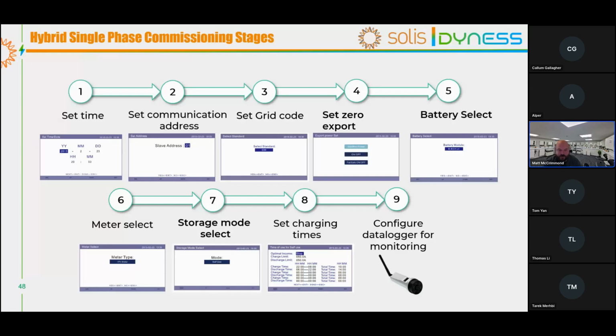You then go into battery select. So in this case, you're going to select Dyness, which is basically the CAN protocol between the inverter and the BMS. And then you should then have communication. You should then see it on the main screen, the battery and its SOC. We'll talk maybe in the next slide about some of the maybe issues you might have in terms of the CAN communication.